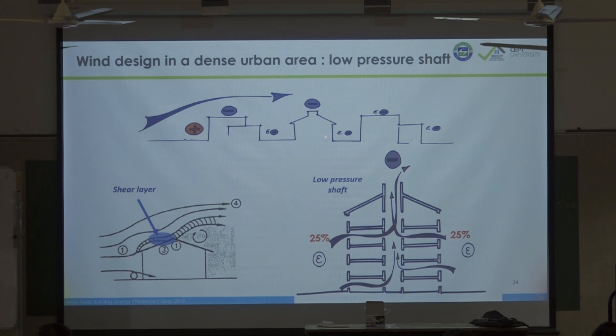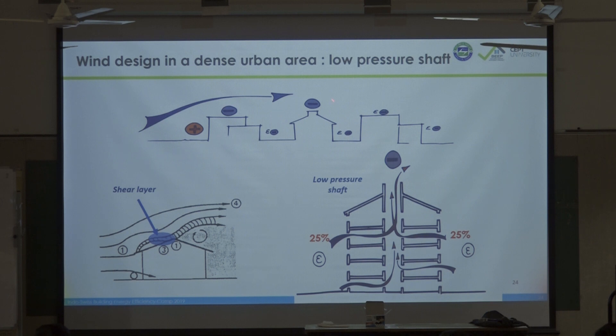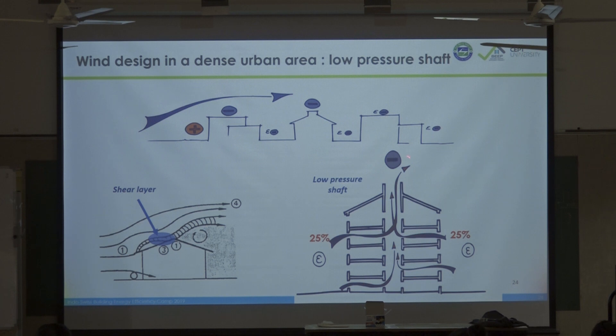If the height of the building is below surrounding buildings, the low pressure shaft won't work. For a multi-story building, you always have to respect 25 percent porosity of openings on each facade, and then you create a low pressure shaft. This is the solution for dense urban areas where using the wind from the street level is not possible.